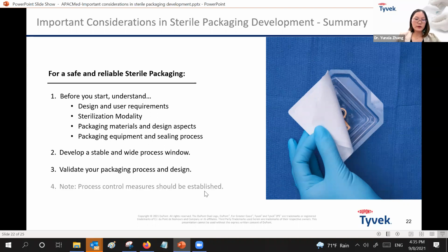I also want to highlight the validation part, because in the new 2019 version of ISO 11607-1, usability evaluation is required, so you need to perform that part as well. And then the process control measures should be established for the process.